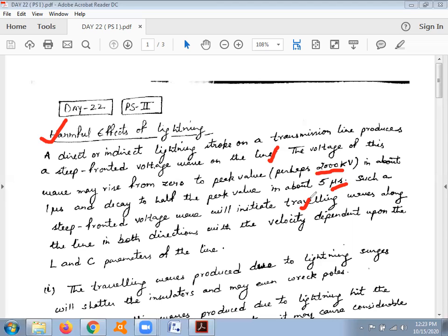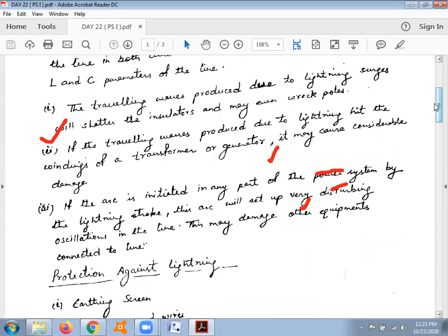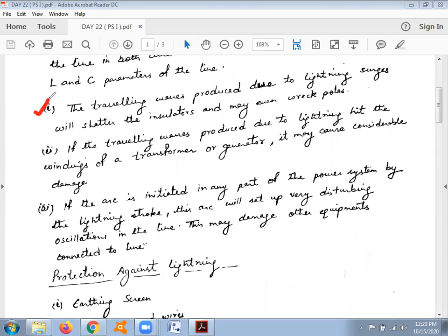The traveling waves propagate with a velocity dependent upon the L and C parameters of the line. There are three key effects: first, traveling waves produced due to lightning surges will shatter insulators and may even wreck poles. Second, if the traveling waves hit the windings of a transformer, they can cause considerable damage to the transformer in a substation or to generators in power stations.